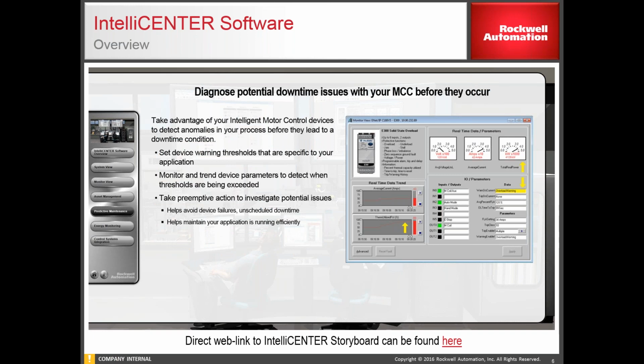So this is what the monitor view looks like. So if you were to drill down on a bucket in the MCC, this is what you're going to get. So there's some meters where you can monitor the voltage or the current. You can set up some real-time trends so you can see what's actually happening. There's parameters that you can modify. If you've got an overload situation and overload trips, you can reset it from the software.